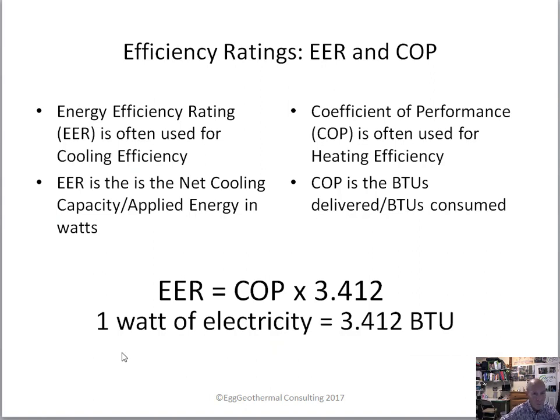Just some conversion factors: a lot of people hear the word kilowatt thrown around, and they'll hear BTUs thrown around. A BTU — which is what air conditioners are regularly rated in — is a British thermal unit. It's the same amount of energy as burning a wooden matchstick from top to bottom, and also the amount of energy it takes to raise one pound of water one degree Fahrenheit. One watt of electricity equals 3.4 BTUs, or 3.4 matchsticks in heat energy. You'll find heat pumps rated in EER (energy efficiency rating) and COP. EER is a little more complex and not needed — most of the world doesn't use it. The US does, but coefficient of performance works both for heating and cooling.